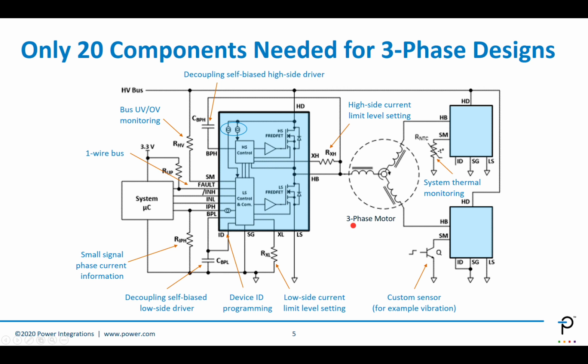Now, the BridgeSwitch also provides the drain current which flows through the low side FREDFET, which mirrors the current which flows through the winding of the motor. In this case, the user doesn't need to add an external shunt, which is required with the competitive solution, and only needs a small signal resistor which is used to amplify the signal which is then sampled by an ADC input on the microcontroller. There is no need for an external op-amp. So such a configuration, of course, reduces the system cost and provides better efficiency by removing the shunt resistor.